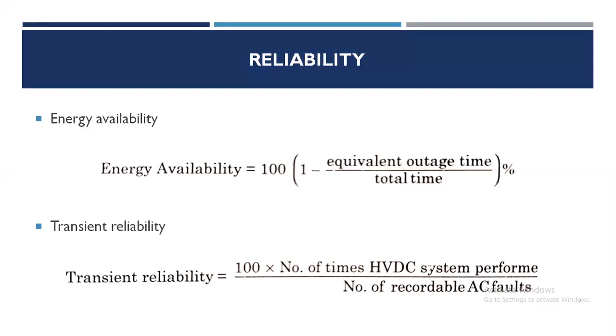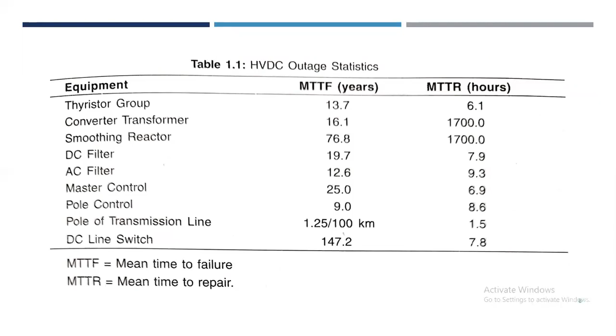In comparing the reliability of various alternatives, it must be kept in mind that a bipolar DC line can be as reliable as a double circuit AC line with same power capability. This is because of the fact that failure of one pole does not affect the operation of the other pole with ground return. If the DC line conductor has adequate overload rating and if the converter on the failed pole can be paralleled with the converters on healthy pole, the pre-fault power level can be maintained even with the permanent outage of one pole.